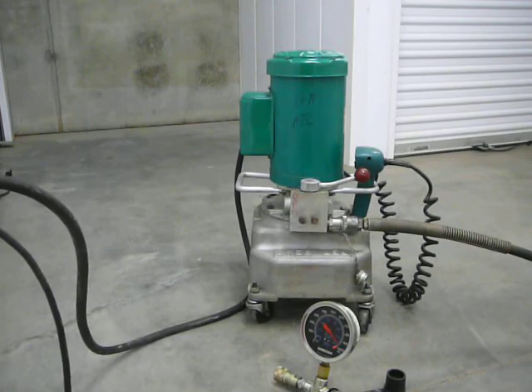It's been about two minutes. You can still see that the pressure is up at least 9,600 pounds. If the valve was closed a little bit tighter, it would probably still be right up there at 10,000. There are no leaks in this pump — it runs just fine.